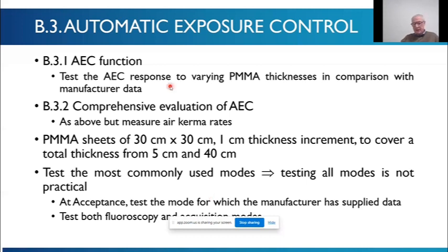And the way that it's done in the protocol is that we do an evaluation where we just vary the PMMA thickness and compare the factors selected by the system to manufacturer data. So we need PMMA sheets, quite large sheets, 30 by 30, maybe 1 or 2 centimeter thickness, to cover the total thickness from 5 to 40 centimeters. You can see this is a large thickness.